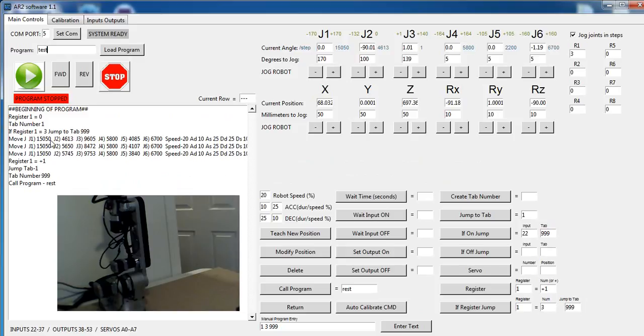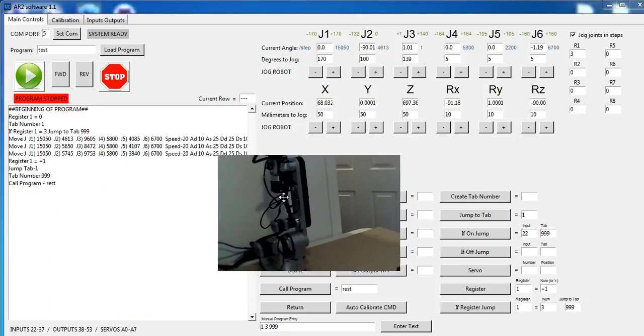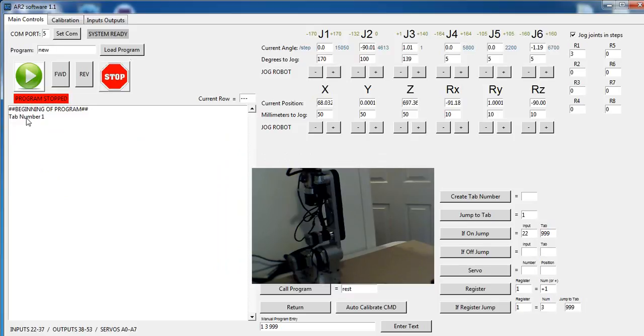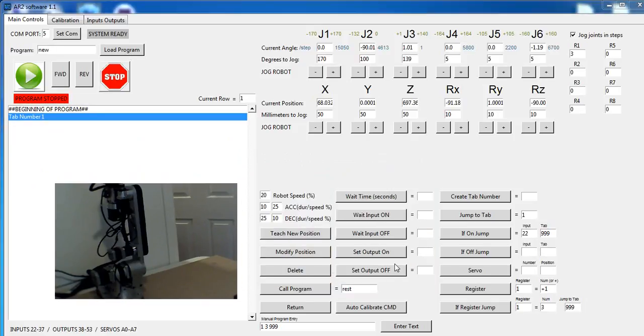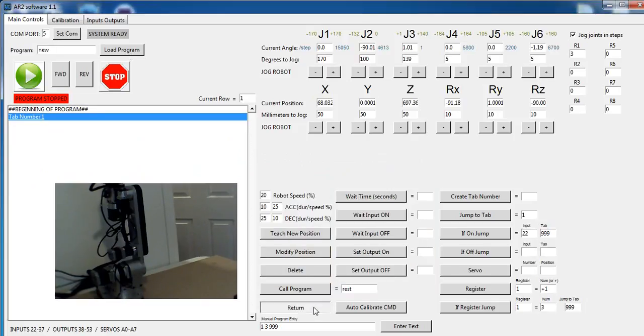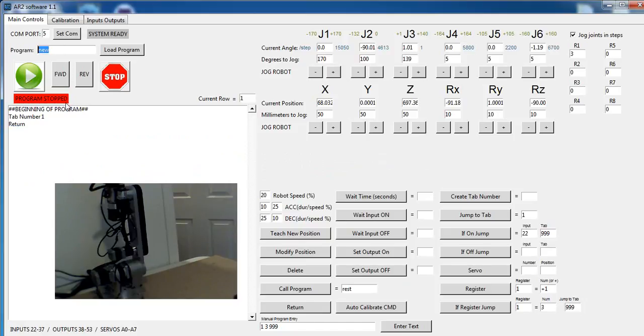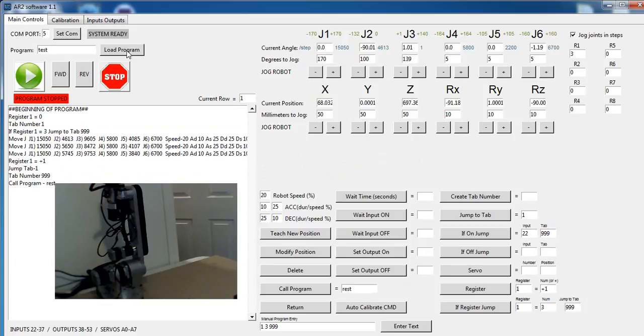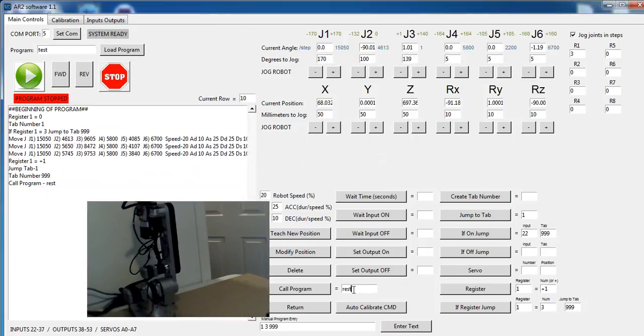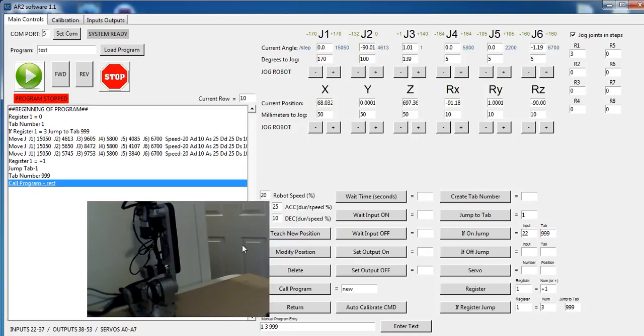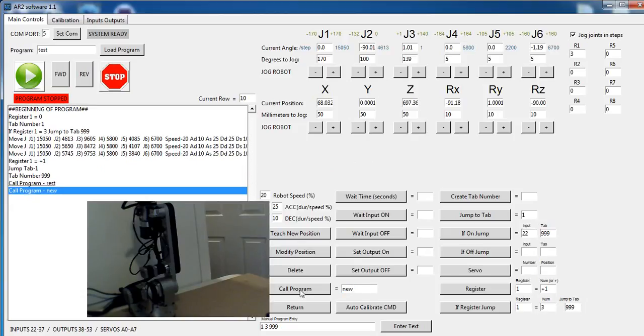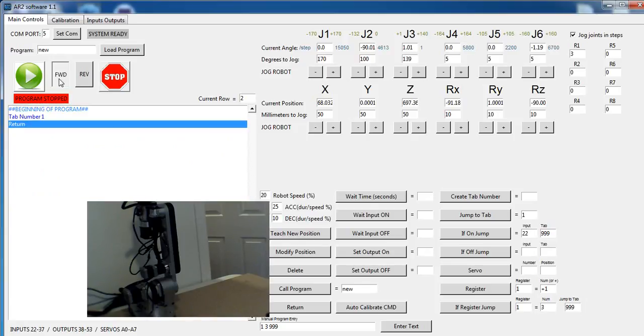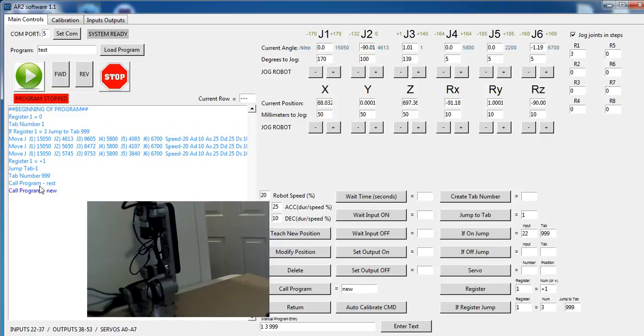If you don't have a return, it won't come back. So, I could basically create a new program, we'll call it new, and then if I do nothing more than just put a return in it, then I can go back to my test program, and I can call new, call program new. So now when I execute program new, it's going to jump into program new, and then when I hit the return, it's going to go right back to where it came from. So you have the ability to jump in and out of programs. You can't go two layers deep, though, you just have to have a main routine that jumps into a program and comes back.